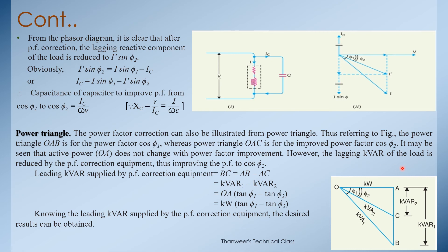The lagging kVAR of the load is reduced by the leading kVAR supplied by the power factor correction equipment. The leading kVAR supplied equals kVAR1 minus kVAR2, where kVAR1 = kW × tan(phi-1) and kVAR2 = kW × tan(phi-2).